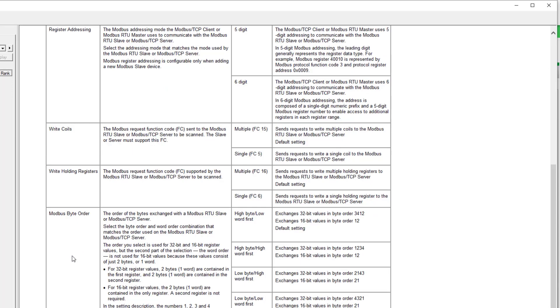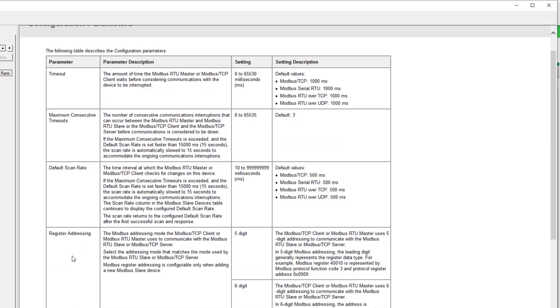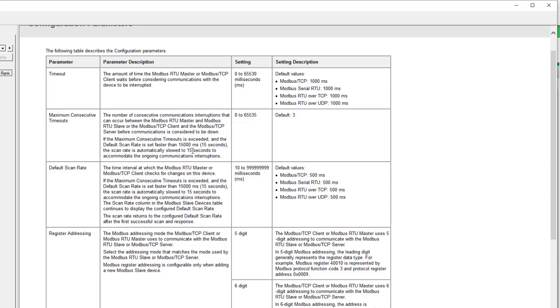F1 opens up help, and this describes everything about each of those parameters. I'll just draw your attention to the timeout value here. This is the number of consecutive timeouts. Note that if you go through three timeouts, perhaps you're testing a disconnection of your cable, that after the three timeouts have occurred, it will slow down to a 15-second poll rate. This is just to accommodate other scanners you may have multi-dropped on the same serial port. It allows those to operate more efficiently while that one disconnection is timing out.